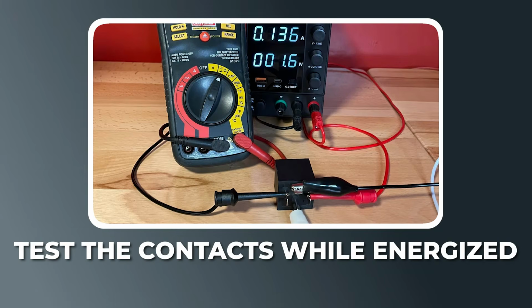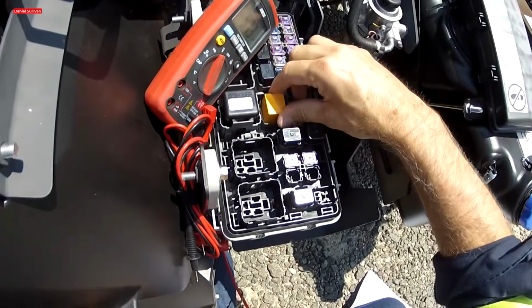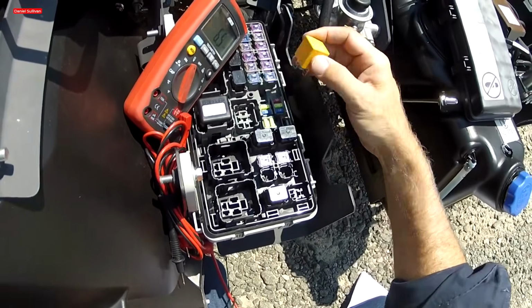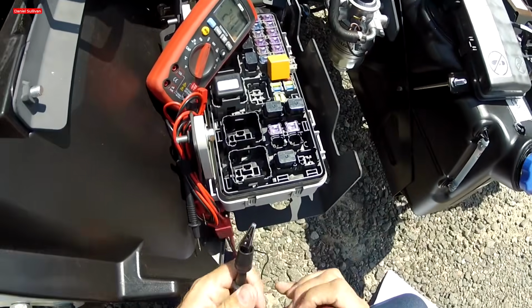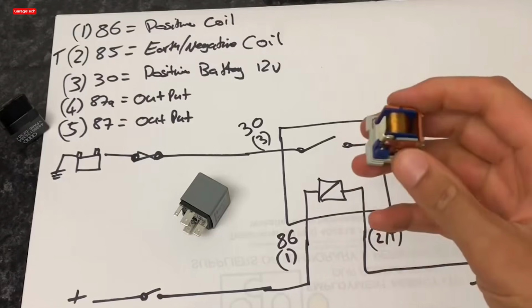Test the contacts while energized. A relay can click and still fail. The internal contacts can be pitted, corroded, or burned from years of arcing.